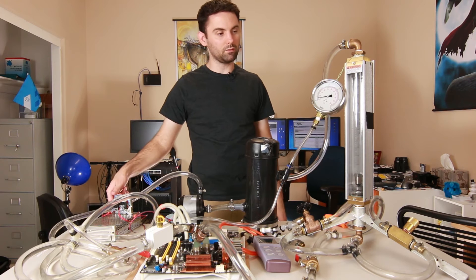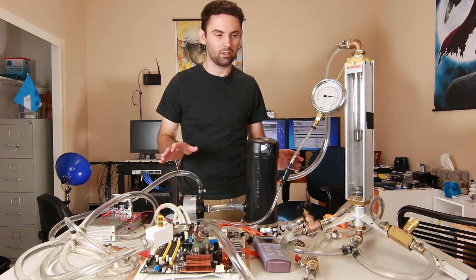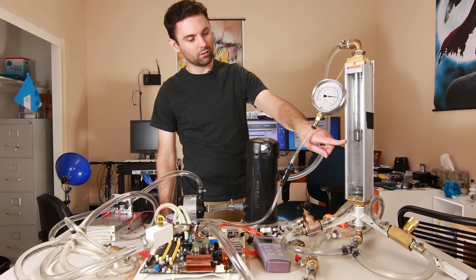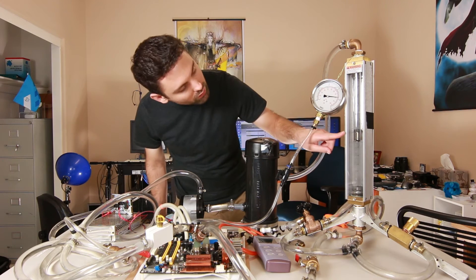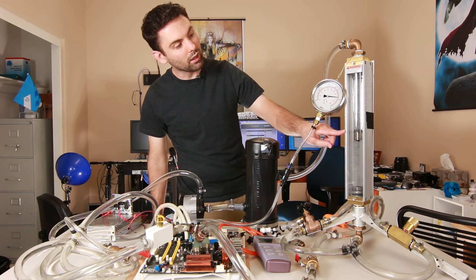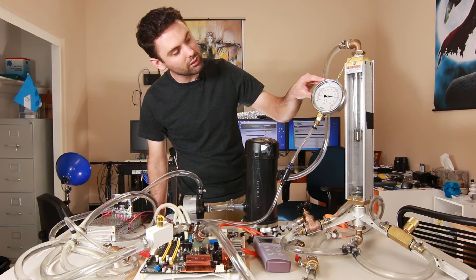So let's get the pump turned on. There we go, there's still a little bit of air in everything, but you can see here pump went on, the gauge is showing, yep, that's about two and a half, 2.6 gallons a minute, and the pump is currently operating at about 13 and a half psi.